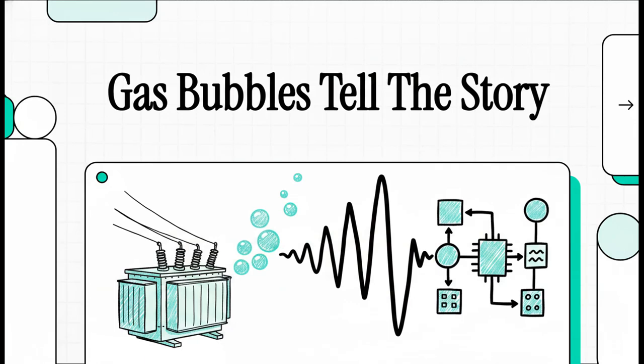Some transformer faults just don't announce themselves electrically at first. A slow-developing internal fault can actually generate gas from decomposing oil long before it produces enough of a current imbalance to trip an electrical relay. But that gas has to go somewhere, right? And the Buchholz relay is waiting for it.